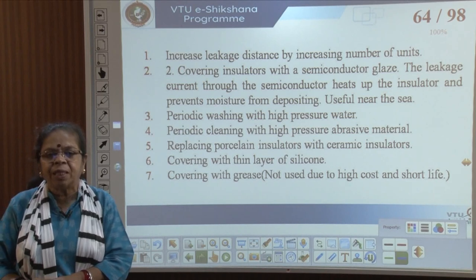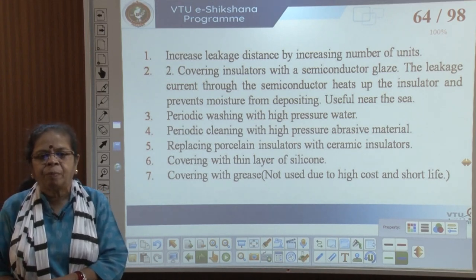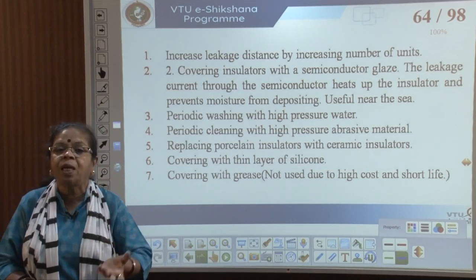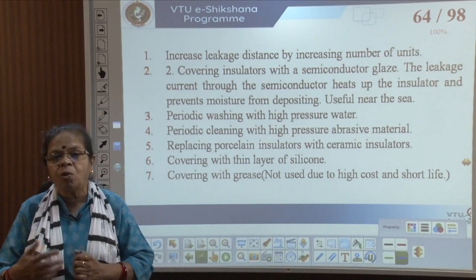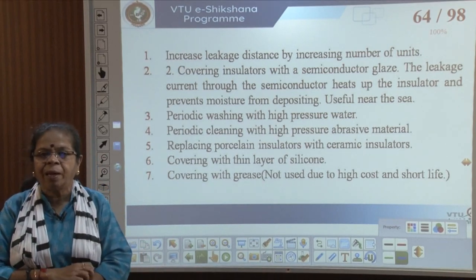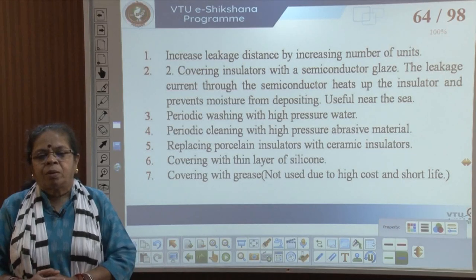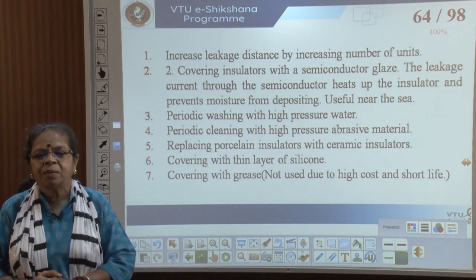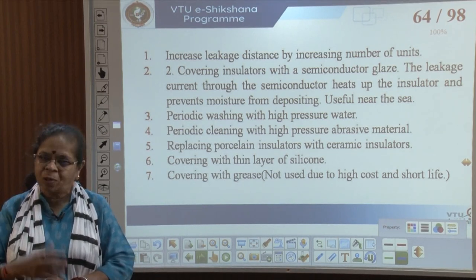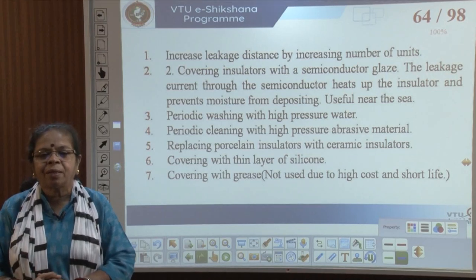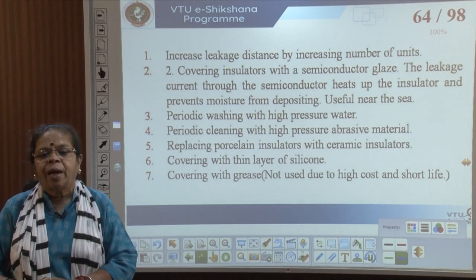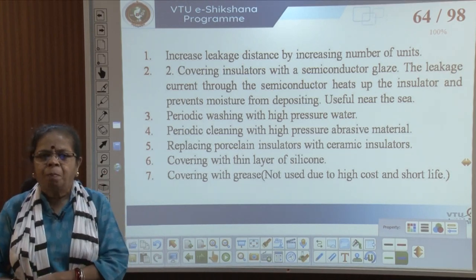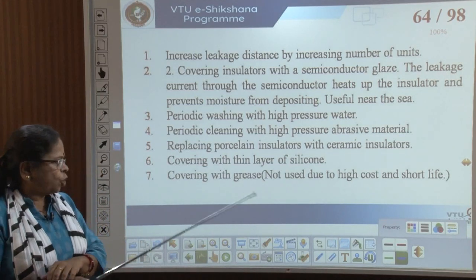We can also replace porcelain insulators with ceramic, or cover the insulator with a thin coat of silicone — which is hydrophobic and doesn't like water. Earlier, grease was used to let water slip off but this is no longer in vogue because we have better options like glazing and silicone covering. Maintenance was a major problem with grease.